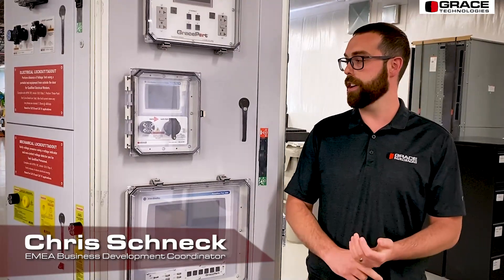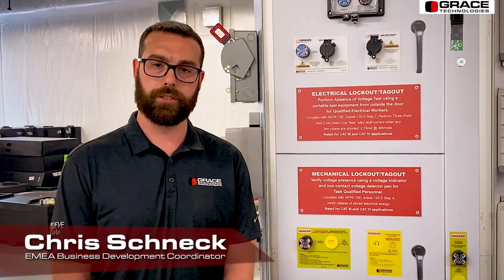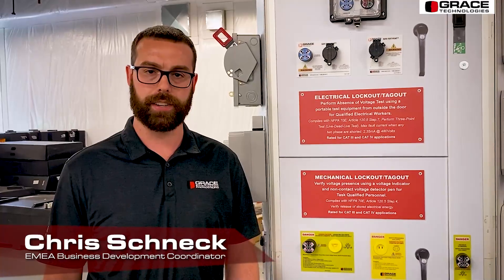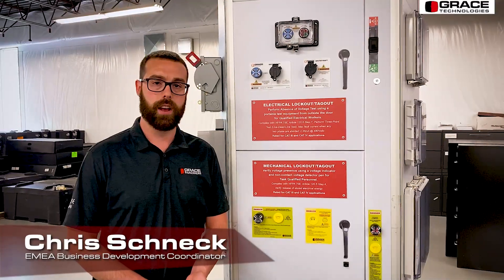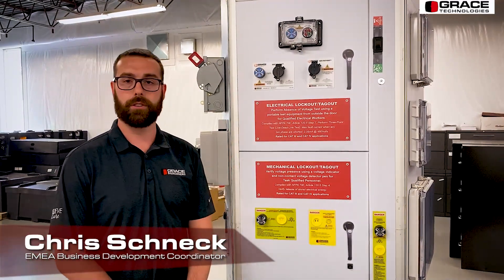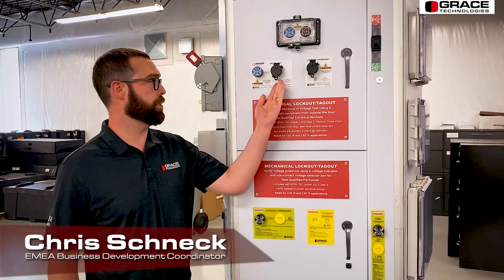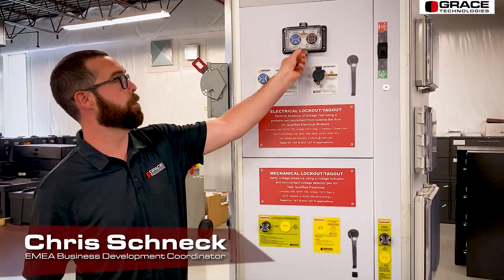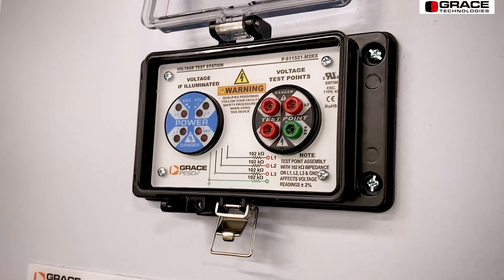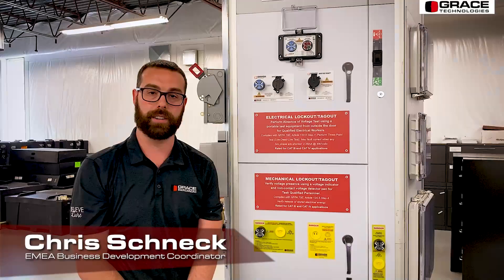These devices carry all of the different UL type ratings, all the way up from UL type 1 to 4X. Our Grace Permanent Electrical Safety Devices, or PESDs as they're commonly called, provide mechanical and electrical lockout and tagout assistance. Our voltage indicator would allow you to verify the presence of voltage for non-electrically qualified workers, while our safe test point gives you the ability to use a voltmeter or a multimeter to physically test each phase conductor, phase to phase and phase to ground, to verify the absence of voltage.